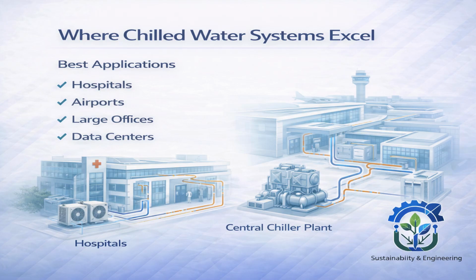Now let's also understand why chill water works well at scale. As buildings grow larger, DX systems become inefficient, and VRF systems hit their piping limits and refrigeration limits. Chill water systems, on the other hand, do not have these constraints. Water is safer than refrigerant, easy to distribute, and suitable for large vertical and horizontal distances. This is why chill water systems are widely used in hospitals, airports, large office buildings, and data centers.